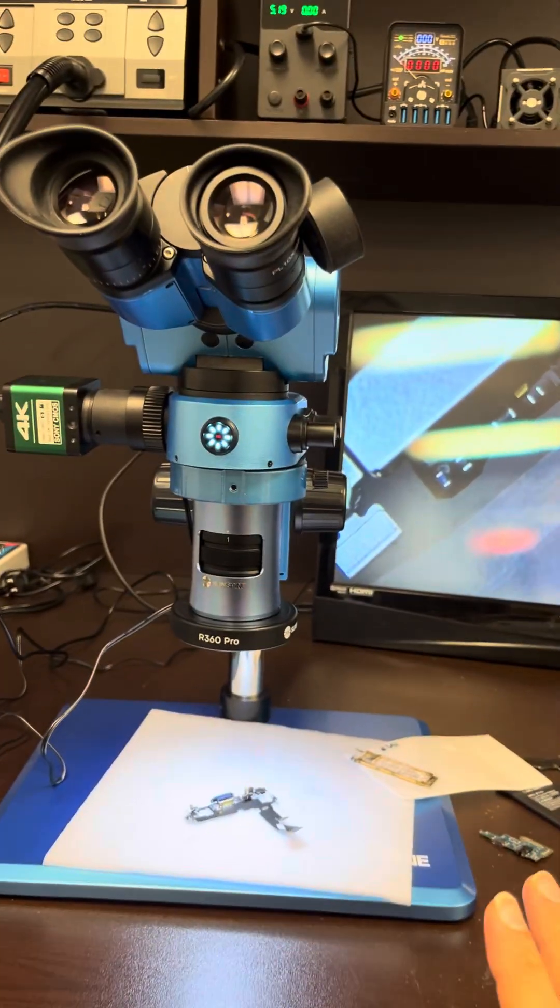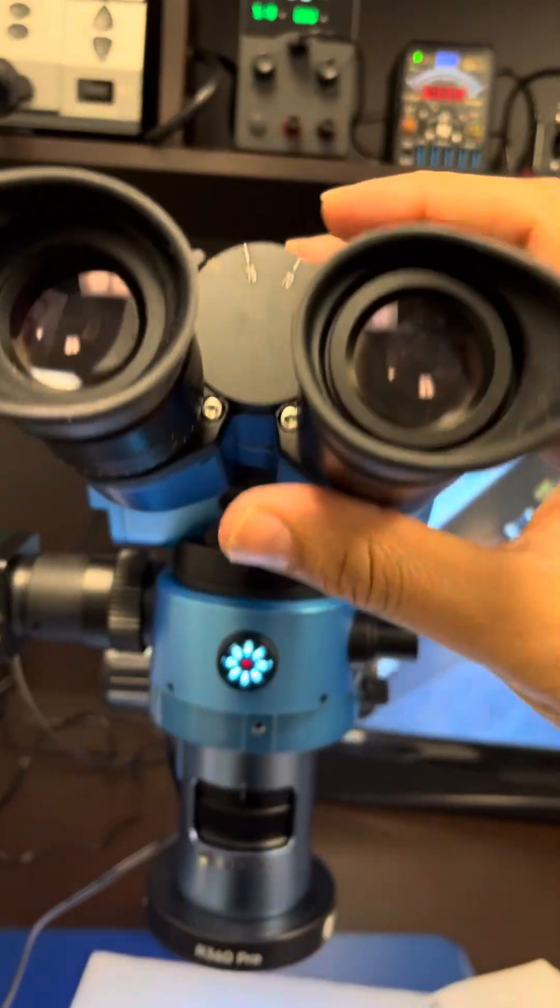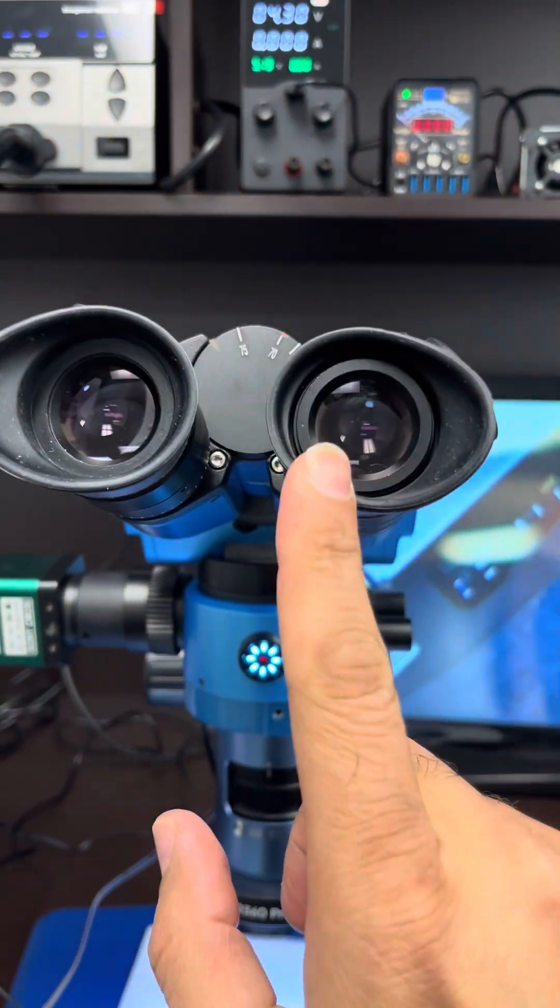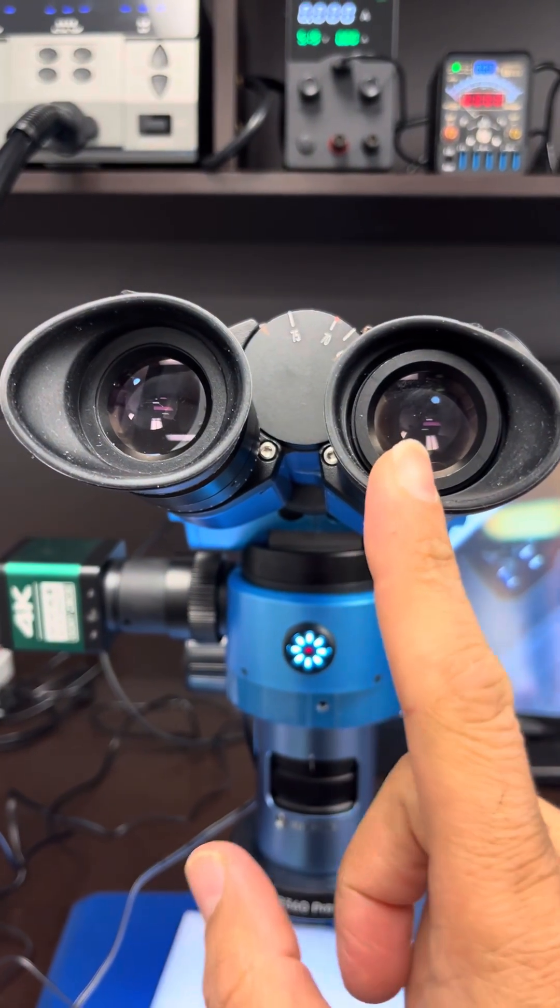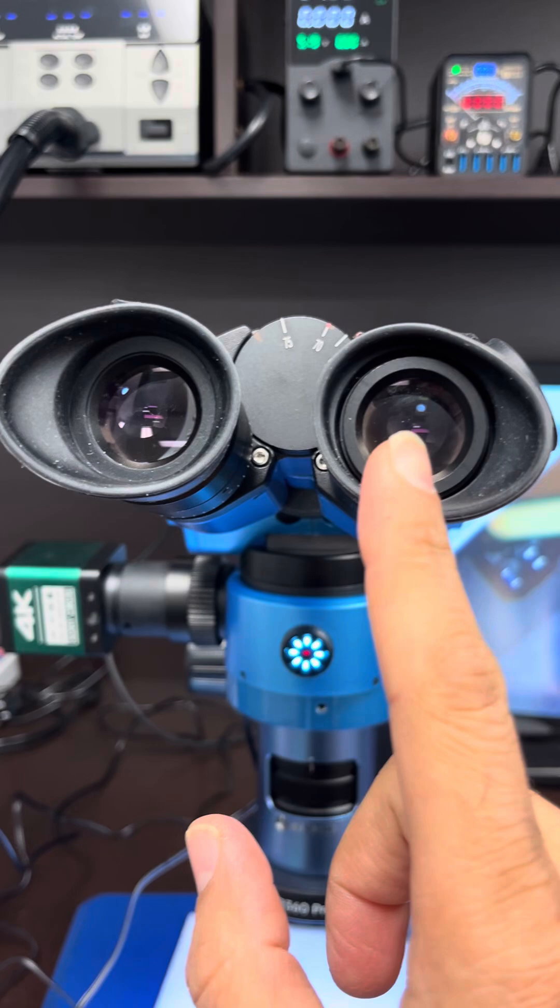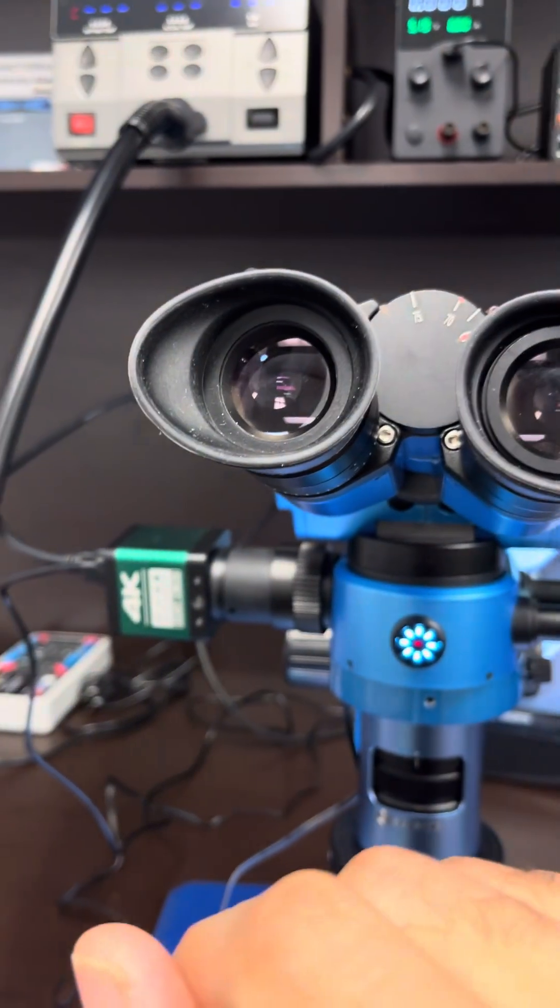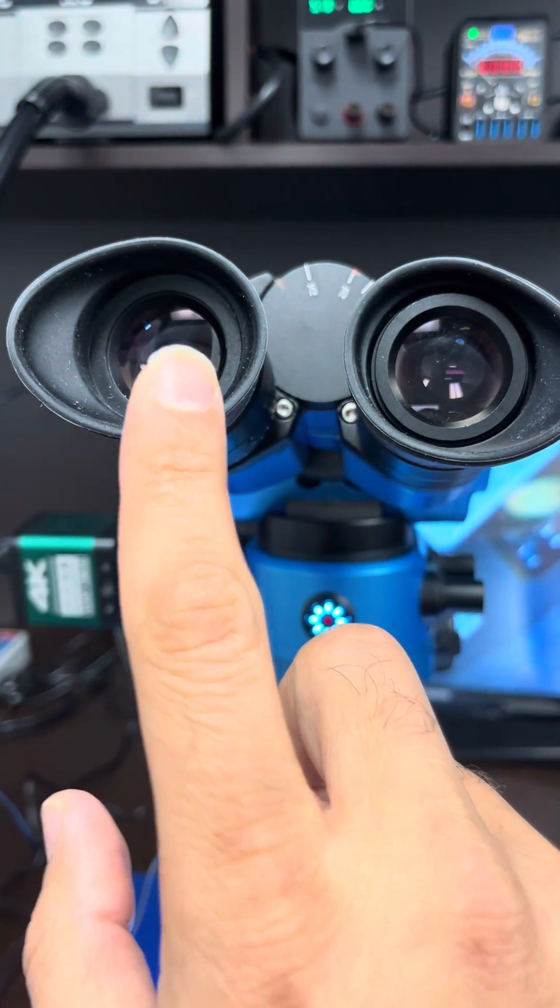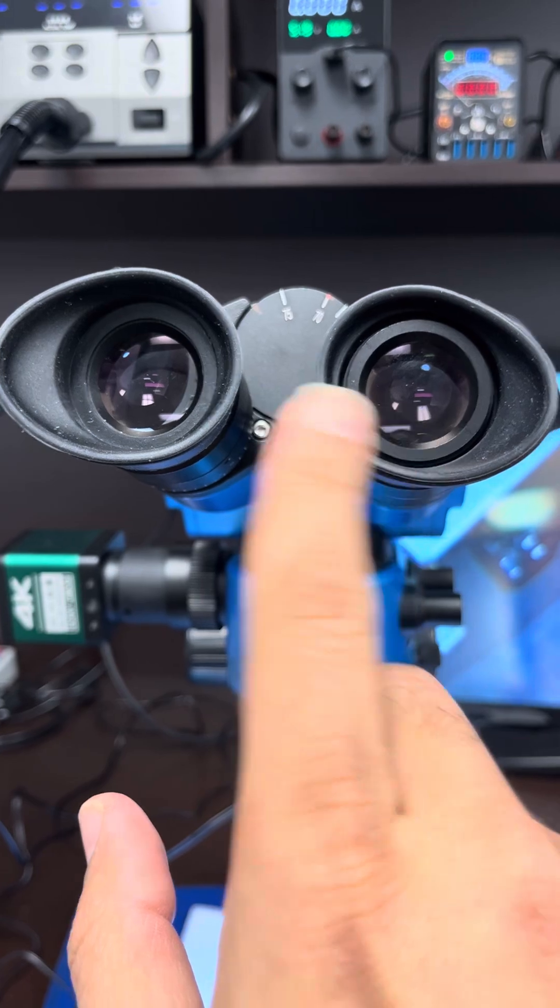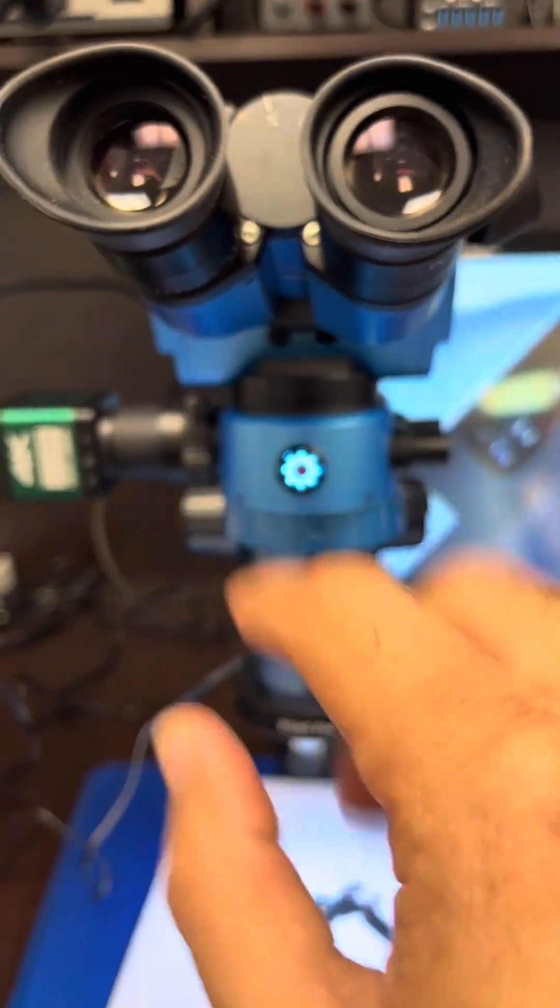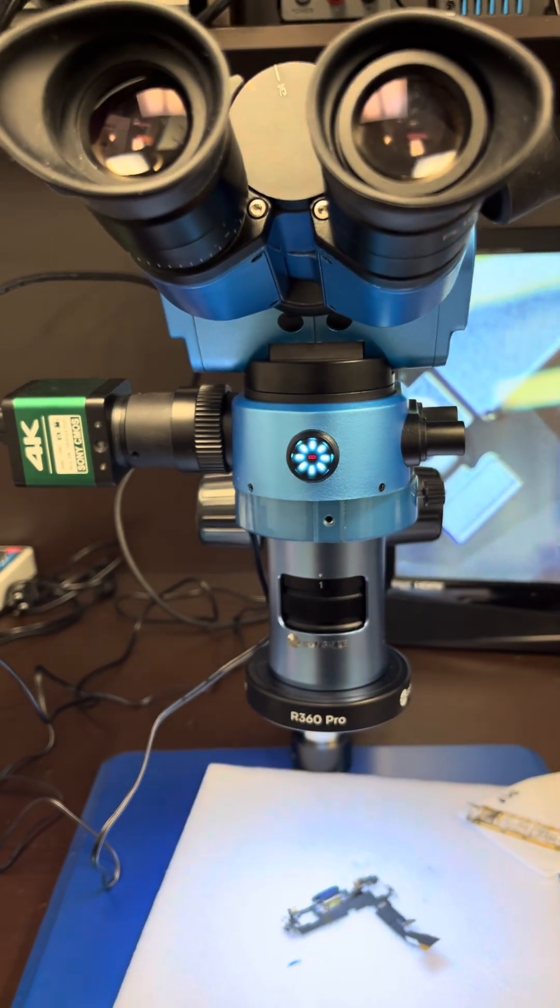Next thing I will tell you is if you are a first-time user of a microscope, how to make a focus. Usually people make two mistakes. First mistake they make is they bring their eyes too close to the lens. You have to make a distance from the lens, you have to make a one-third inch difference from the lens. And second mistake they make: when they look inside the microscope, they focus on the lens. You don't need to focus on the lenses, your eyes should focus on the object. When your eyes focus on the object, it will automatically synchronize both eyes.